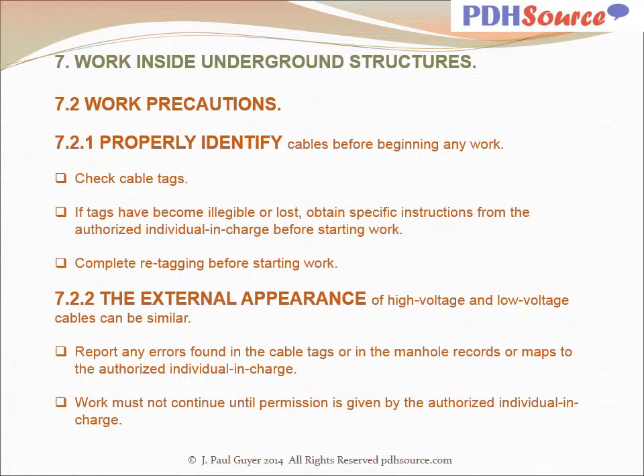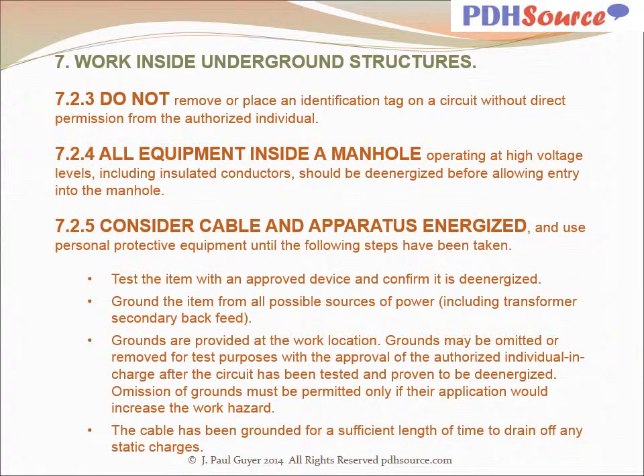Properly identify cables before beginning any work. Check cable tags if tags have become illegible or lost. Obtain specific instruction from the authorized individual in charge before starting work. Complete retagging before starting work. The external appearance of high voltage and low voltage cables can be similar. Report any errors found in the cable tags or in the manhole records or maps to the authorized individual in charge. Work must not continue until permission is given by the authorized individual in charge. Do not remove or place an identification tag on a circuit without direct permission from the authorized individual.